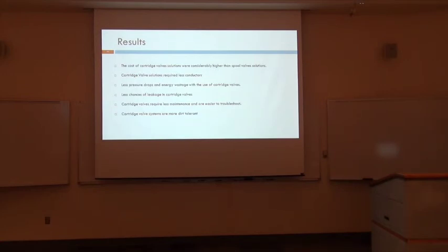We also found out that cartridge valves experience less pressure drop and thus less energy wastage compared to spool valves. And why is that? With spool valves, the fluid has to go over the spool, so there's an increase in friction, and also with more conductors, that also increases friction. There's a correlation between friction and pressure drop. With more friction, you have more pressure drop, and there's a correlation between pressure drop and horsepower. And so if you have more pressure drop, then you waste more power.